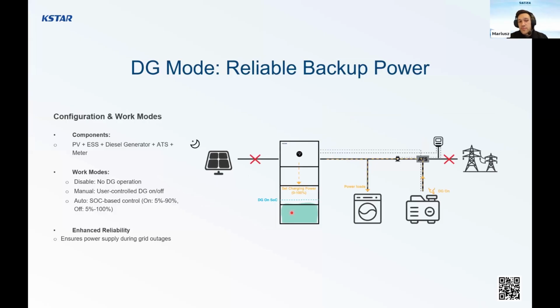The backup power we can combine with the diesel generator. Of course, we need an external ATS, which is compatible with the diesel generator, because we don't have a diesel generator input inside our inverter, but we can do the communication with a dry normally closed or dry normally open contact.